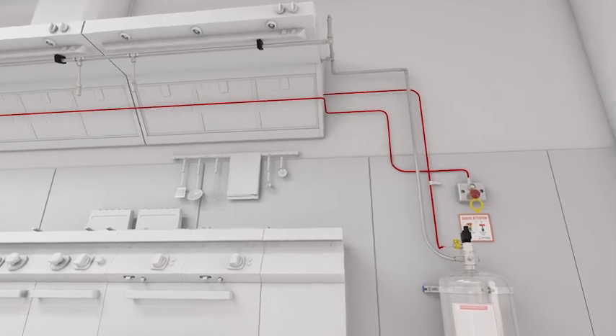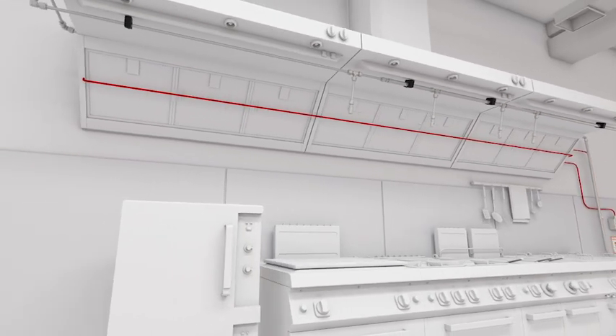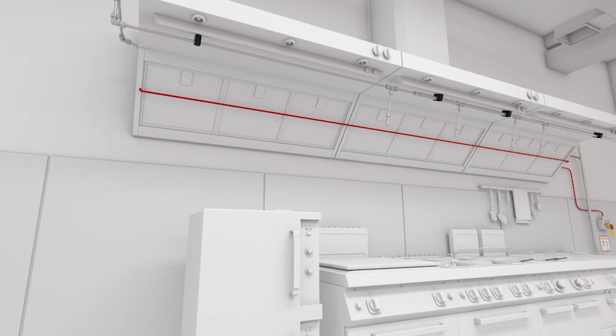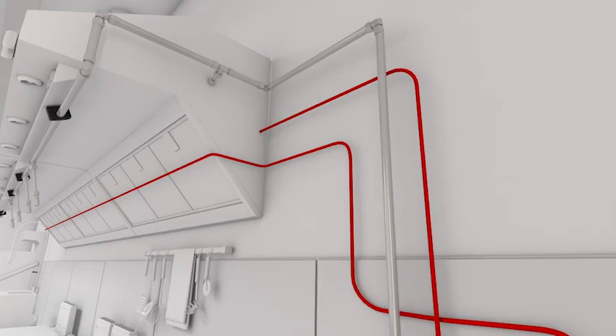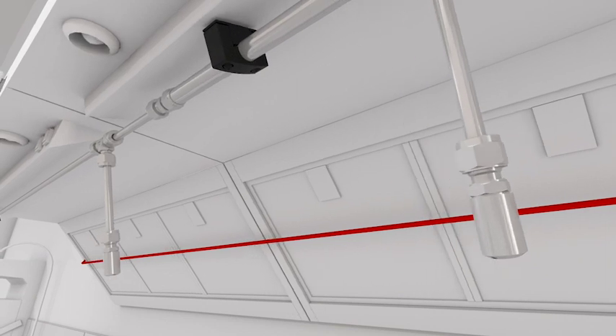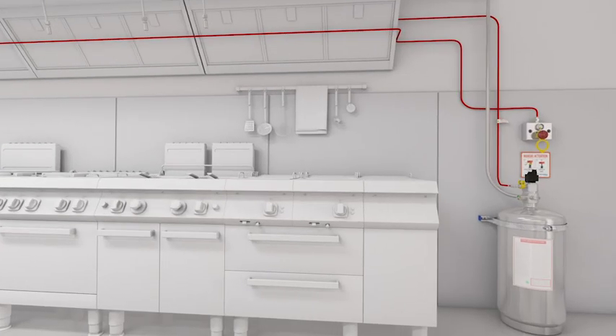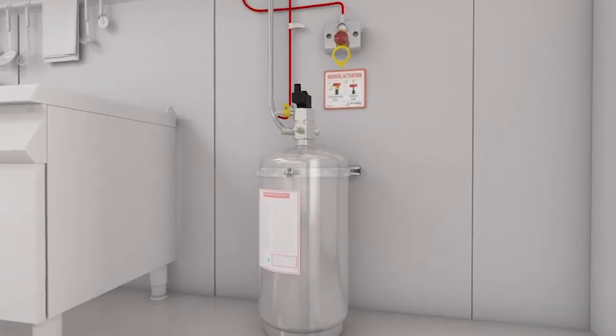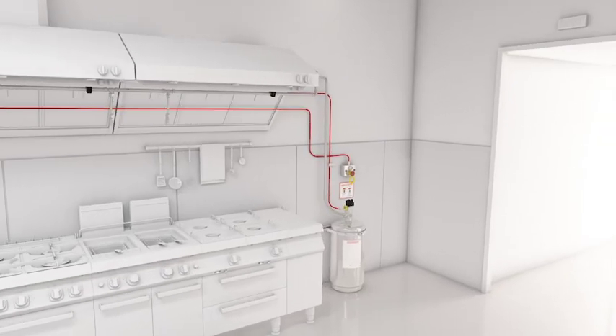This little pressurized tube makes the difference. Our simple pneumatic technology is extremely reliable and detects a fire very quickly. The detection tube installs directly into the kitchen hood, directly over cooking areas. It's flexible, so it installs easily, adapting to the unique shape and geometry of your equipment. One end is connected to the valve. The other end is attached to a manual actuator mounted visibly near the cooking zone, somewhere along the fire exit path.